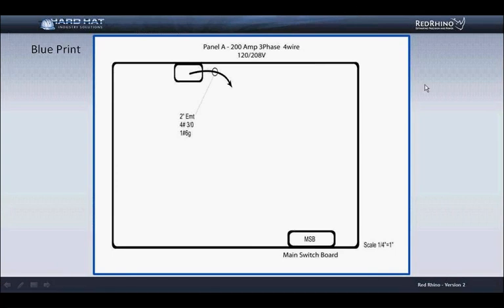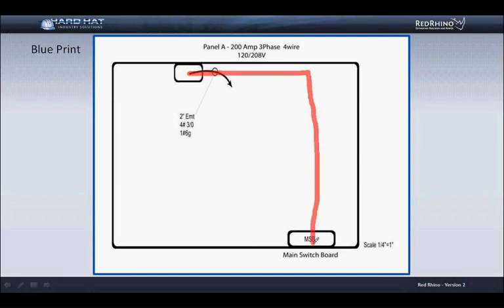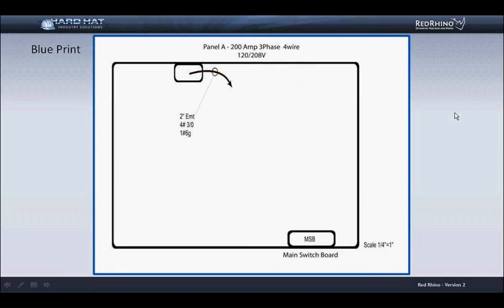Here's a tip for taking off conduit. Takeoff all conduits at right angles to the plan. Do not measure on diagonals. By measuring at right angles, you allow enough conduit and wire to go around obstacles or obstructions in the building. When rolling off or measuring conduit, it's essential to include the conduit riser length in the takeoff.